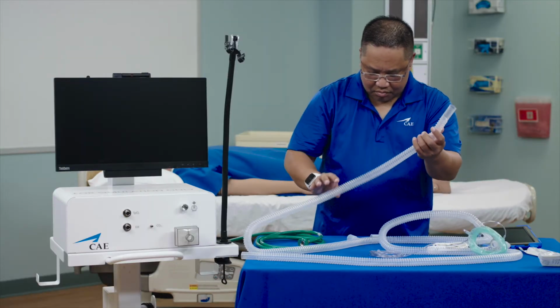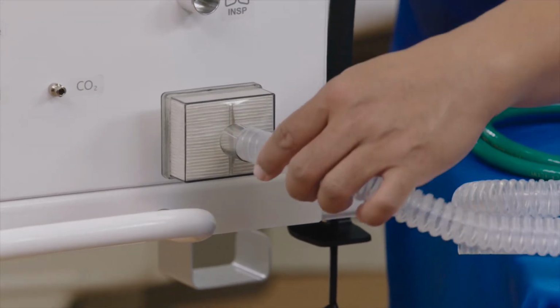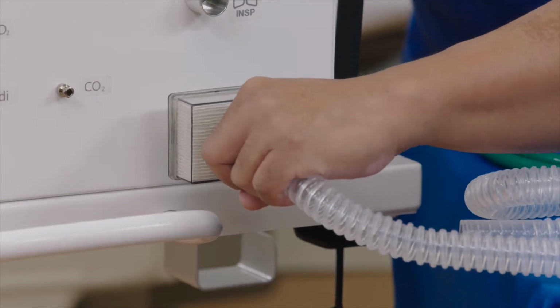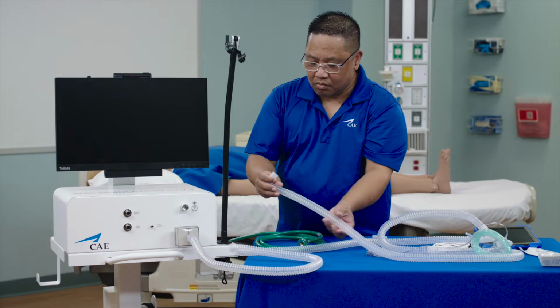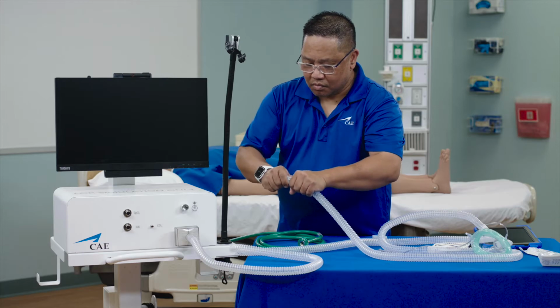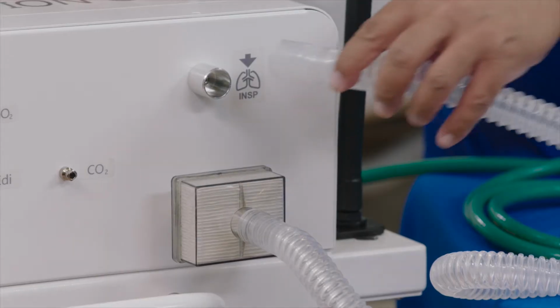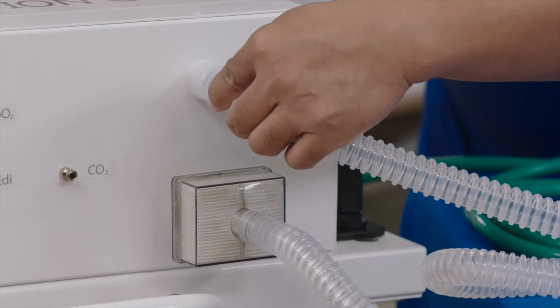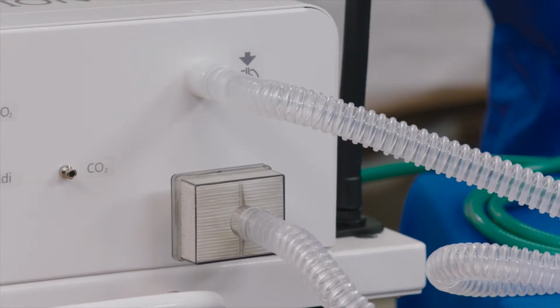Connect one of the limbs from the breathing circuit to the filter on the cart front panel. Connect the hose cuff to the second limb of the breathing circuit. Connect the second limb to the cart front panel port labeled INSP. Hose cuffs may also be used on the breathing circuit before connecting to the filter.